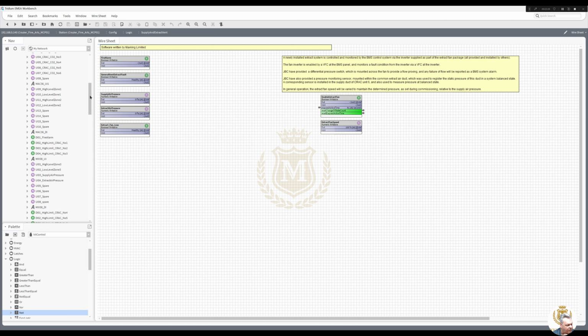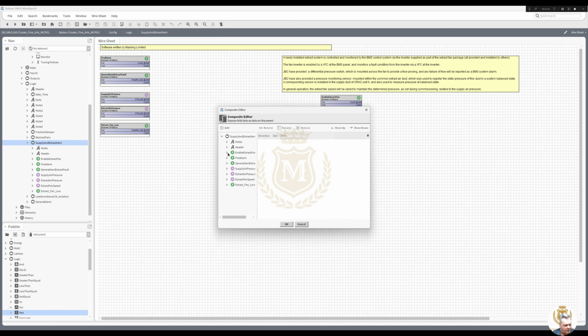So let's composite these points across. I always like to open up the folder on the left so I can see the points I've done, which are all there in this. I'm going to right click that, go to composite. So I'm going to put my fire alarm at the top. Well, I'll tell you what, I'll do it the same order as this so I know what's what, and then I can re-change it later. So that's going to be an output. That's going to be an input. That's going to be an input. That's going to be an input. That's going to be also an input. That's going to be an output.